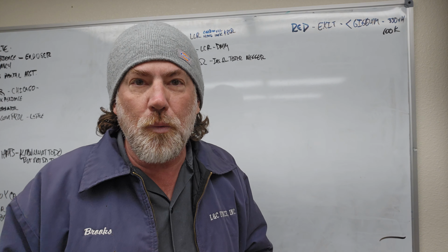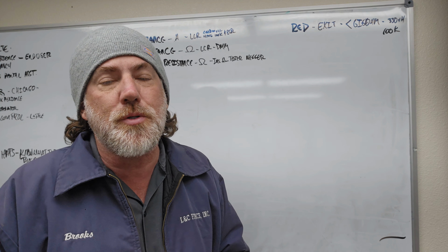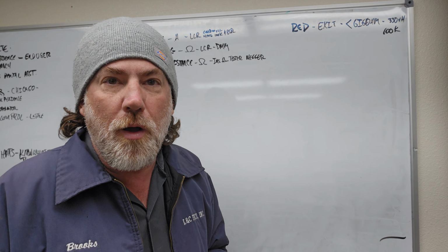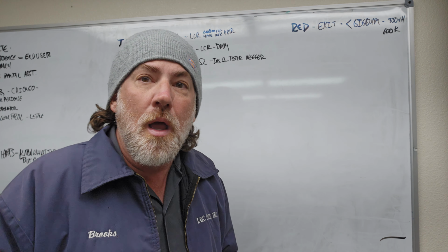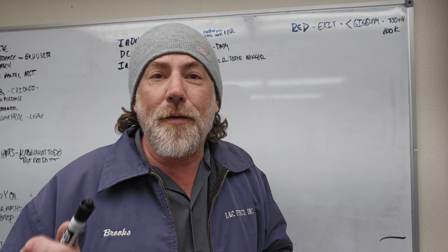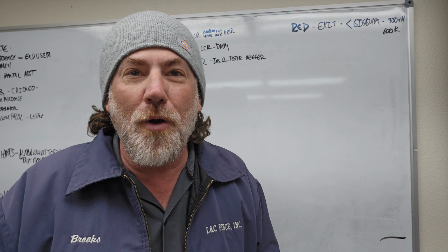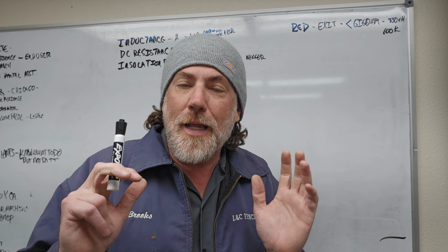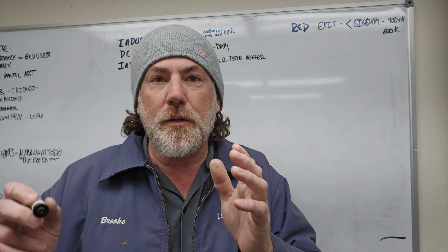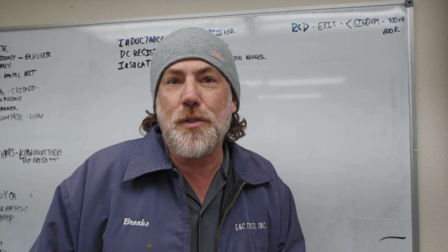The common device that you would use to do that is actually an LCR, which measures inductance, capacitance, and resistance, which is the reason why I was saying just press that button over to R and you could test the DC resistance as well too. And what that allows you to do is, if you have a good insulation test, whether you actually have continuity in the loop, because you can have a good insulation test and actually no continuity on the loop. And that's why it's flawed to go to your Megger first. I'm not saying that it's the wrong thing to absolutely do, because it could be in this process, but it's the wrong thing to do just by telling people to do that and not understanding that DC resistance or continuity is actually an important factor.